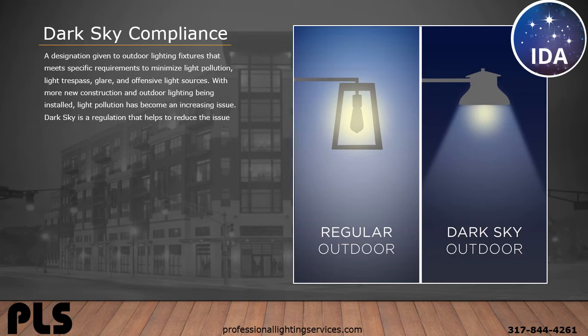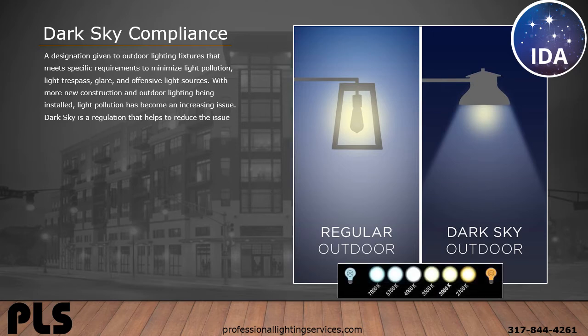The color of light is important as well. Blue-rich lighting brightens the night sky more than warm-colored lighting, and researchers are beginning to connect the blue light emission to negative health effects in people and greater problems for wildlife. The International Dark Sky Association, or IDA, recommends using lighting with a color temperature of 3000 Kelvin or less.